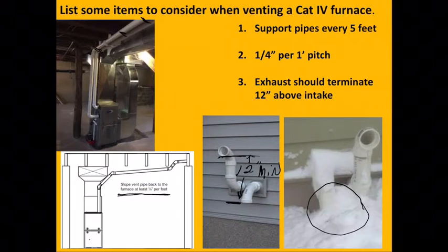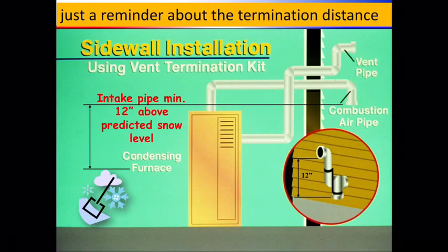So in my first house, I had some water lines that actually froze up, and the contractor who had installed the furnace in the house before I had purchased it, they had probably at best 6 inches above the grass, and that was all it took, was the wrong winds, and things will happen. So snow intake level is a big one.